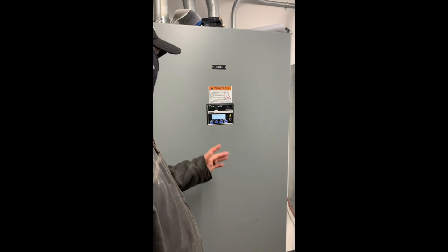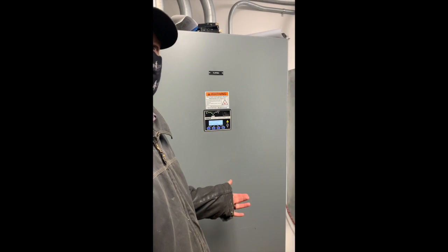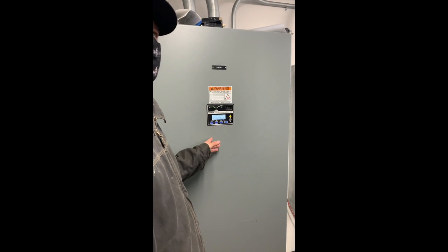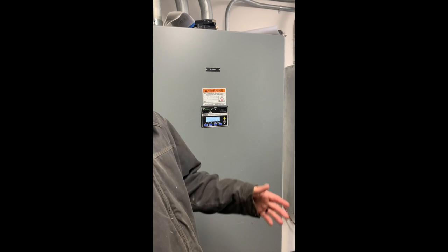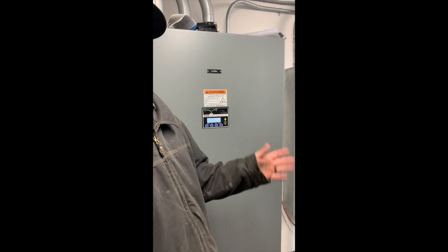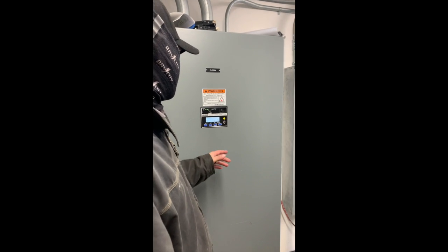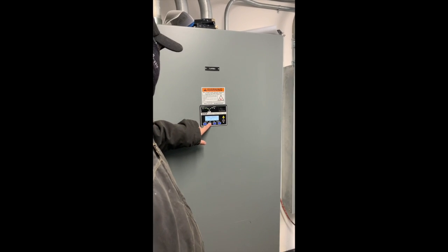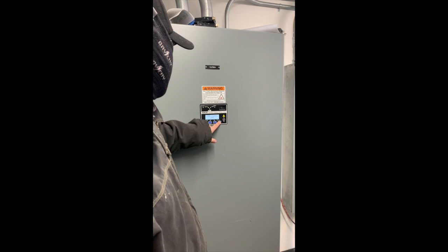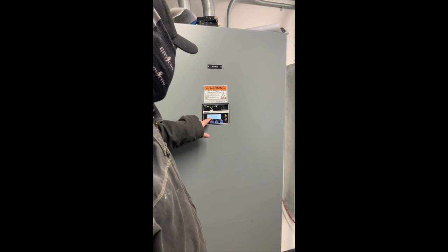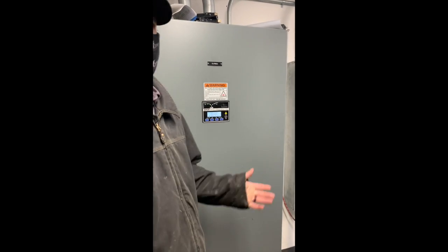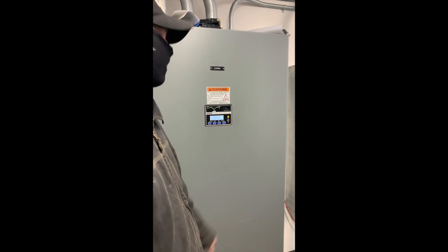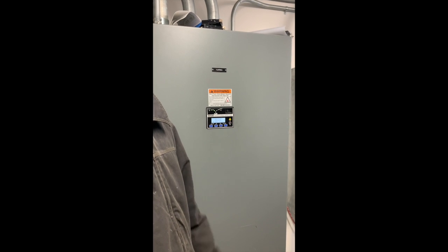Now say you wanted to do the transfer one. You would do the exact same way, but you would do that loaded test. Then it would transfer and run as long as you wanted until you transfer back manually, so it doesn't time out. I was going to show you, there is one that's a timer, right here, but it's auto loaded, so it's a loaded test, and it's for 30 minutes. You hit start, and it would run 30 minutes, and then shut down after 30 minutes.